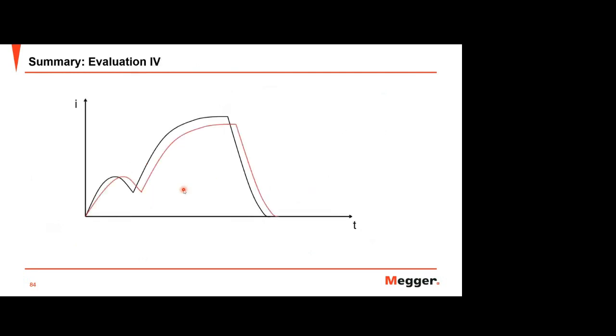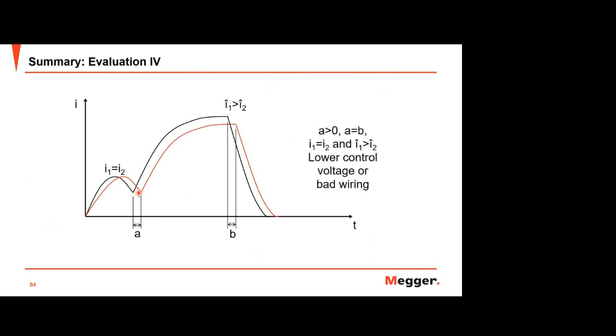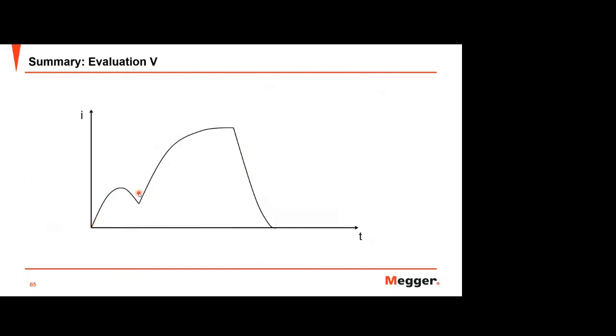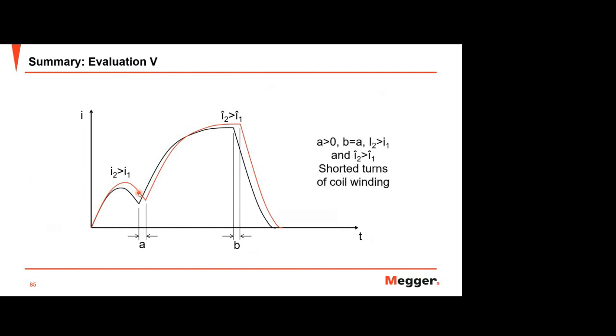And the next evaluation is like this. The current is still the same on the coil, but has a little delay. Mostly this is caused by low control voltage or bad wiring. So you can investigate whether the voltage level is the same as before or not, or maybe there is bad wiring on the coil circuit. And evaluation 5 is a combination of 3 and 4. Sorry, this is different. If you see that I2 is higher than I1, and also has a delay compared to the reference result, but the delay is the same between A and B, it means shorted turns of the coil winding. So still a problem on the coil.